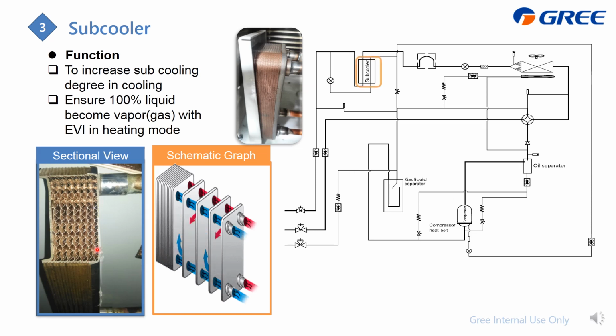The purpose is just to ensure the refrigerant to become completely gas. So in cooling, we can higher the subcooling degree, which include this part. And in heating, we can ensure, as we would like to adopt the EVI, which is to inject the vapor or the gas to the compressor here inside it, and which means at this outlet it should be 100% vapor or gas. How we can achieve it is use this subcooler. The refrigerant will first get expanded to become low pressure and temperature, then it can absorb heat from the main row. Then itself will become the gas or the vapor, then into the EVI.